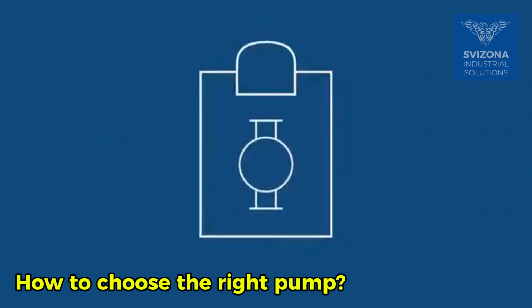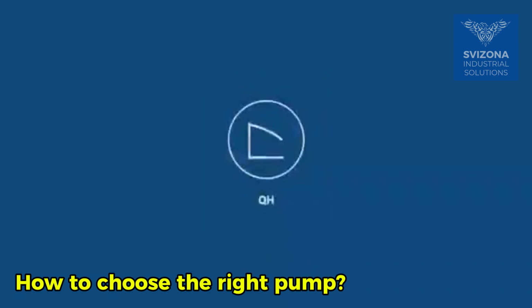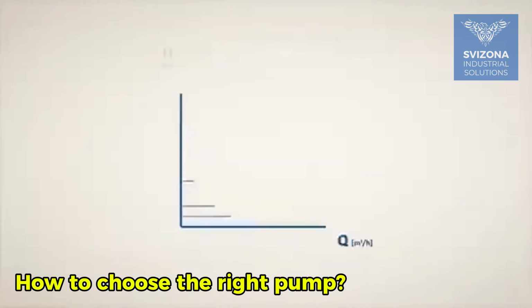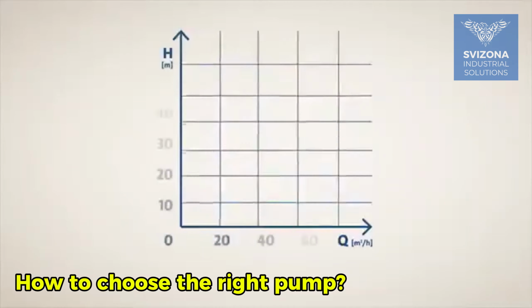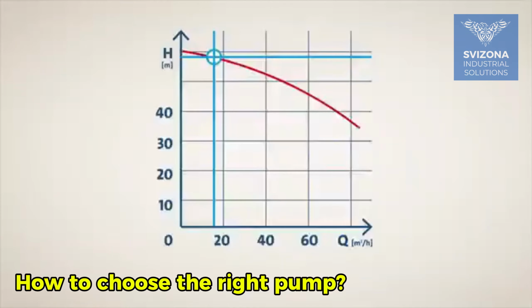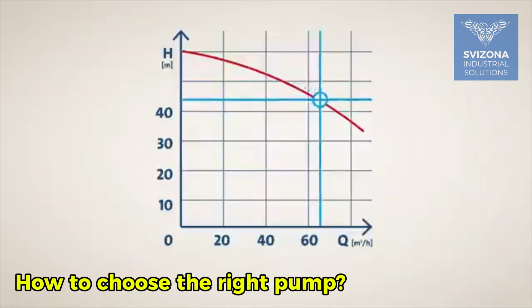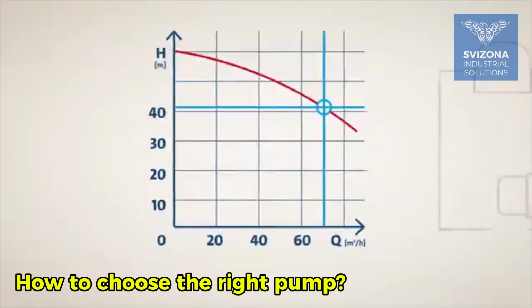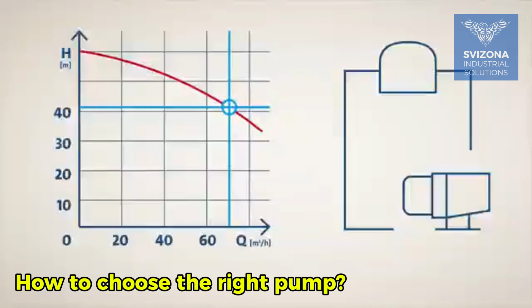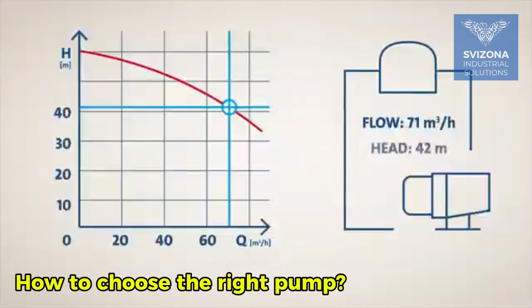In a QH curve, which measures the flow and head, you can see that a low flow results in a high head and a high flow results in a low head. Once you have identified the requirements for your application, the flow, Q, and head, H, will help you determine the overall dimensions of the pump. In this example, you can see that a flow of 71 cubic meters per hour equals a head of 42 meters.